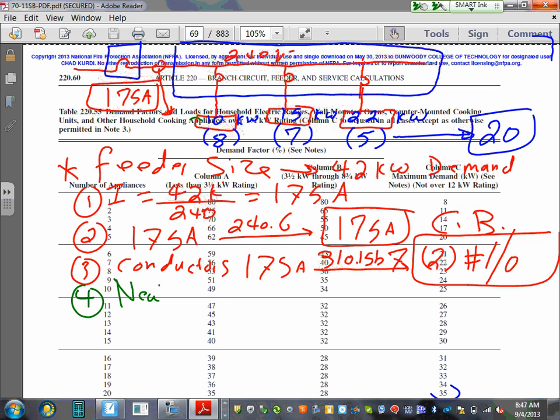Neutral conductor. For the neutral conductor, what you have to do is take 70%, multiply it by the size, 175. Do me a favor, what's 70% of 175? 122.5, 123 amps. Cool? 123 amps.